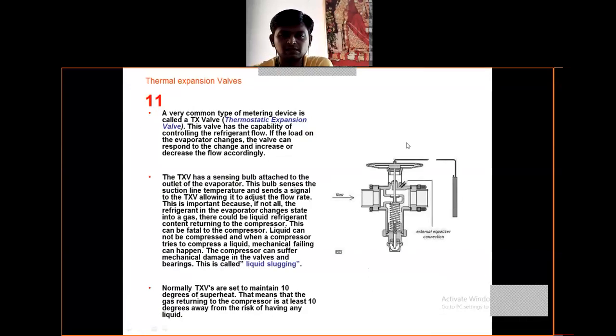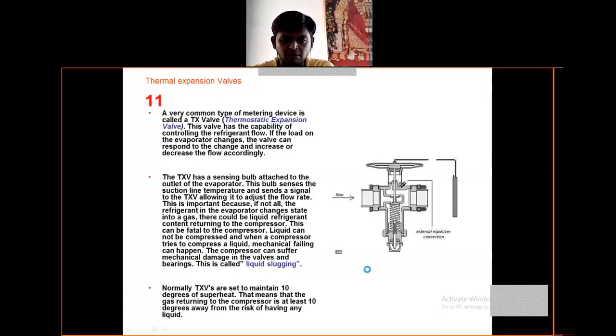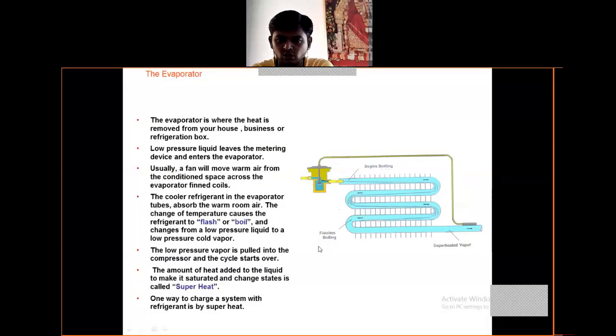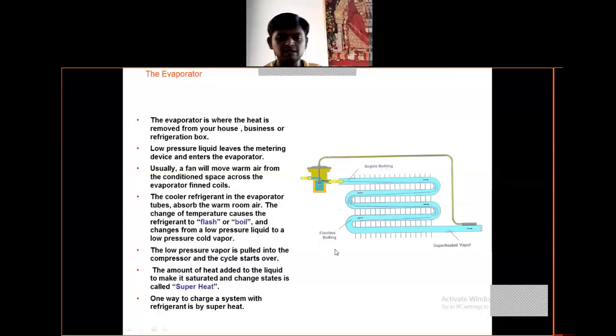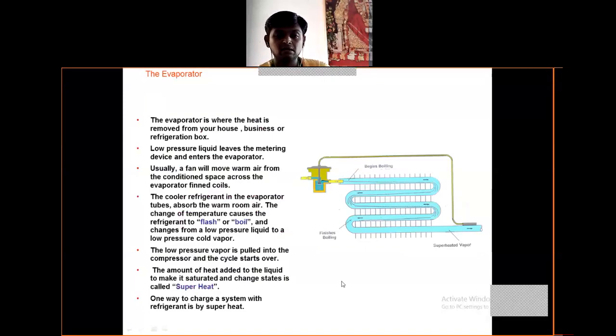This is the thermostatic expansion valve. It has the capability of controlling the refrigerant flow. If the load on the evaporator changes, the valve can respond and increase or decrease the flow accordingly. The evaporator is where heat is removed from your house, business, or refrigeration box. The heat added to the liquid to make it saturated and change its state is called superheat. The cooler refrigerant in the evaporator tubes absorbs warm room air, and the change in temperature causes the refrigerant to flash or boil.